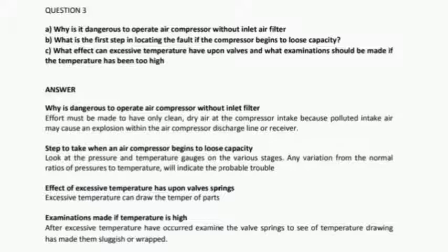Effect of excessive temperature on valves. Excessive temperature can cause wear of the valve. It can cause the valve spring to become weak. It can also cause carbon accumulation on the valve seat. This can lead to the valve not seating properly or getting stuck in either the open or the closed position, which can lead to a reduction in the efficiency of the compressor.